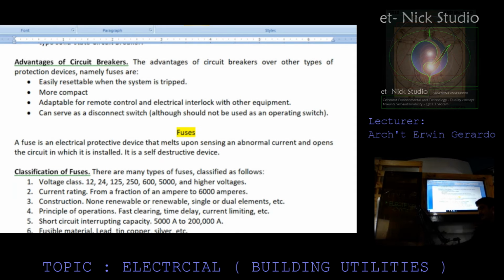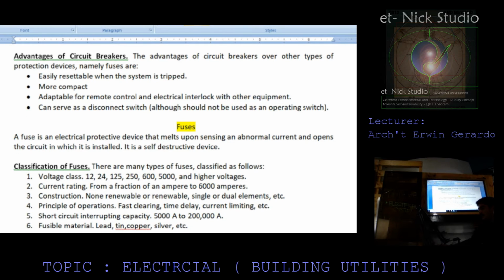Advantages of circuit breakers. The advantage of circuit breakers over other types of protection devices, namely fuses, is that they are easily resettable when the system is tripped, more compact, adaptable for remote control and electrical interlock with other equipment, and can serve as a disconnect switch, although they should not be used as an operating switch.